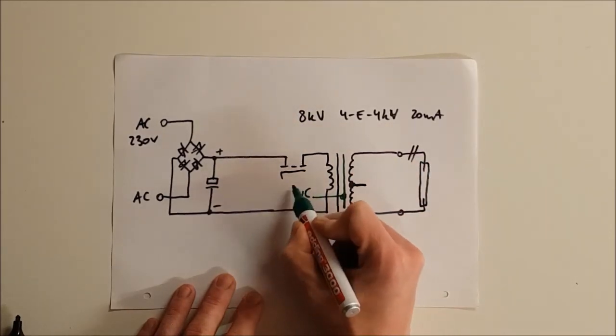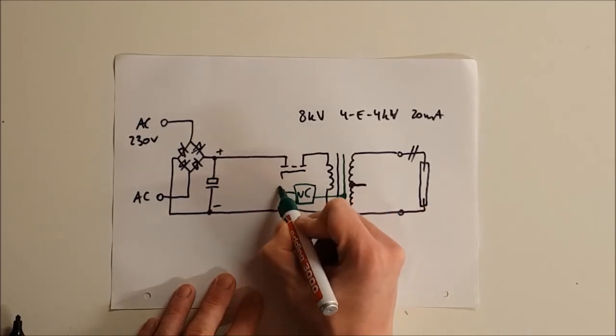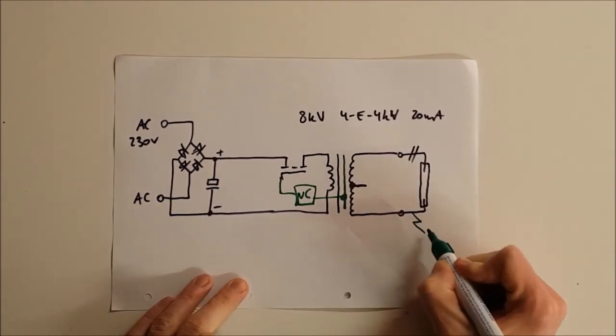Put to a microcontroller, and then the microcontroller can operate this power transistor to shut the transformer off. That's one way to do the open secondary detection. The ground fault detection can work just in a similar way as on the classic core and coil transformer if we have a ground fault here.